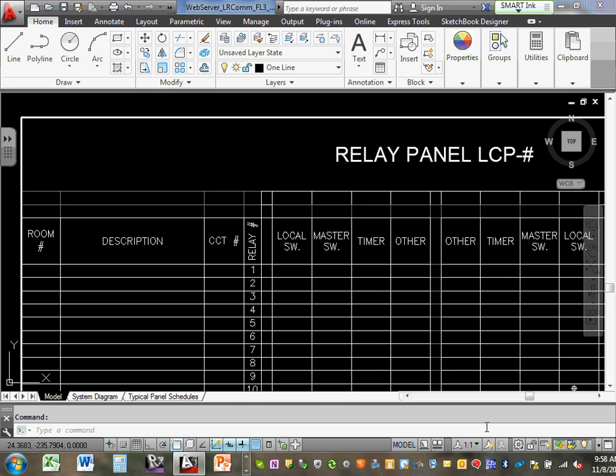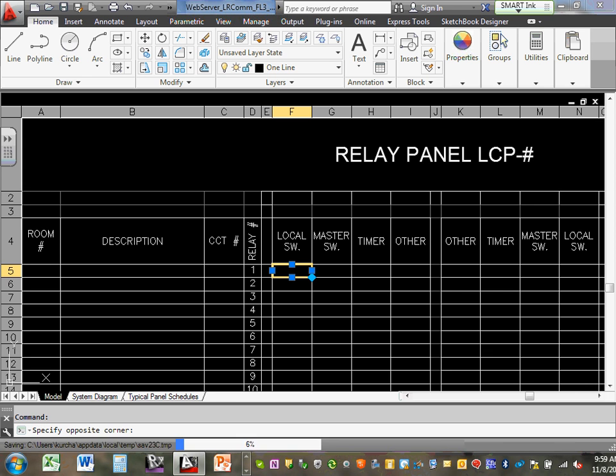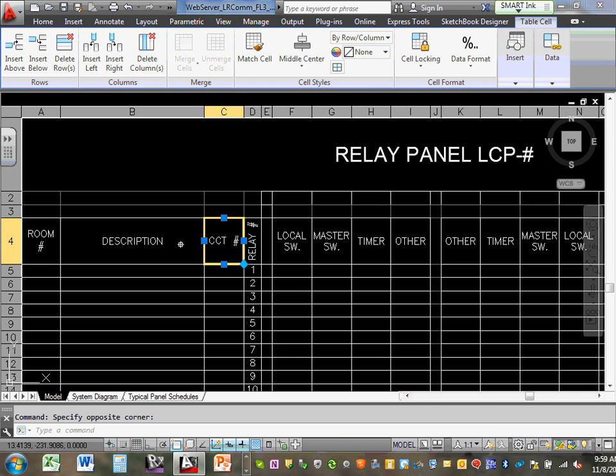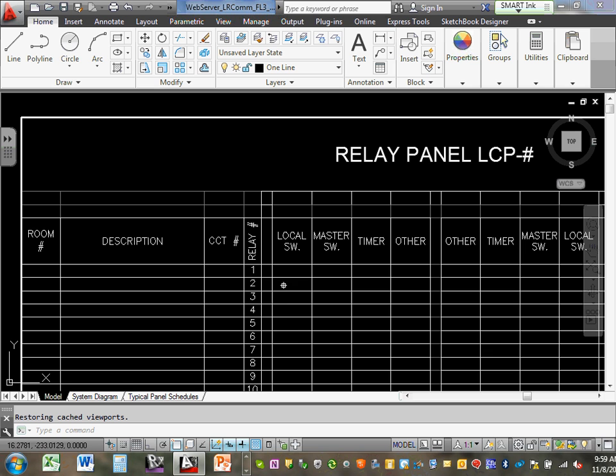So when we expand this out, we want to know whether it's a local switch or a master switch. When we deal with master switch stations, typically it's in an admin office, head custodian's office, something like that, where I want a master switch station that can do multiple things. I want to be able to control big chunks of the building that I can't see. So in the admin building, in an office or a large library, I do have switches out in the space, but I've got an override at the master station that I can shut things down with. So it could be a local switch, and then we could have a master switch tied to that same circuit, right? So that could be local switch number 1, master switch number 1.